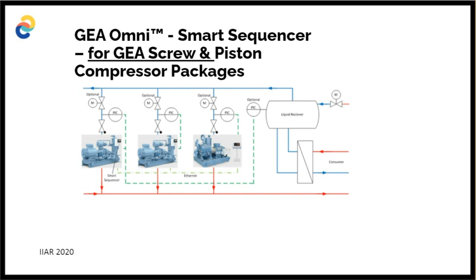And the smart sequencer also looks at the size of the compressors, as I mentioned, and it will balance those machines to give the most efficient operation at any given moment in time. So if we see the opportunity to switch a large drive motor off, replace it with a smaller machine or a smaller drive motor, then Omni will automatically do that for you in the smart sequencer.